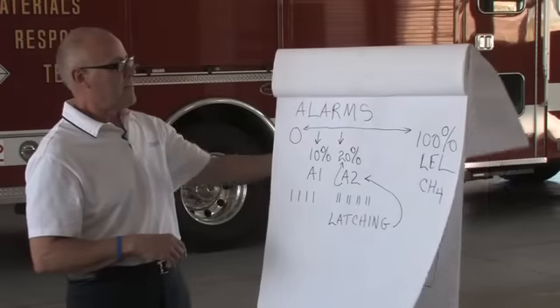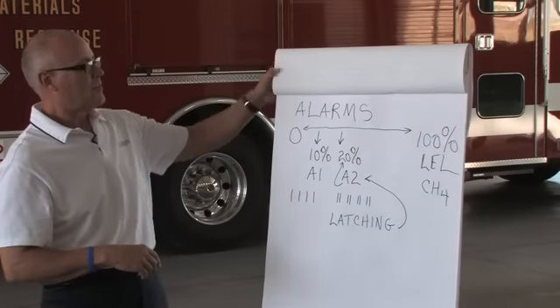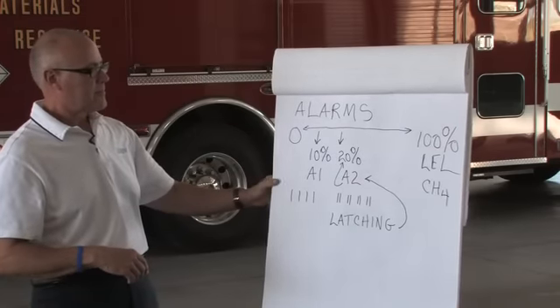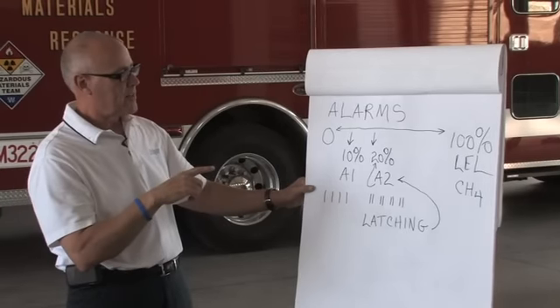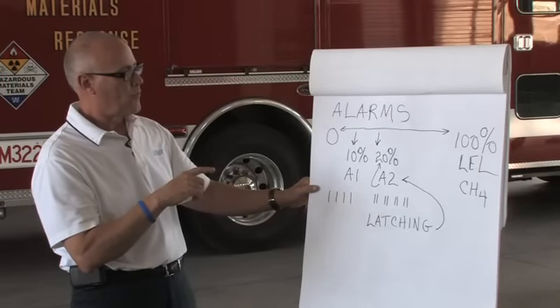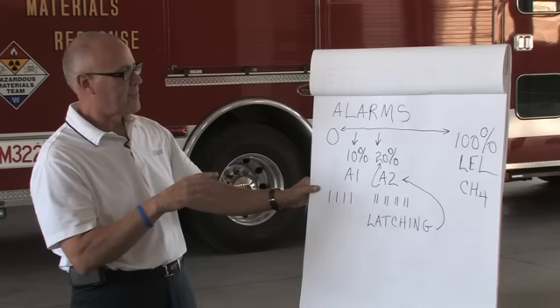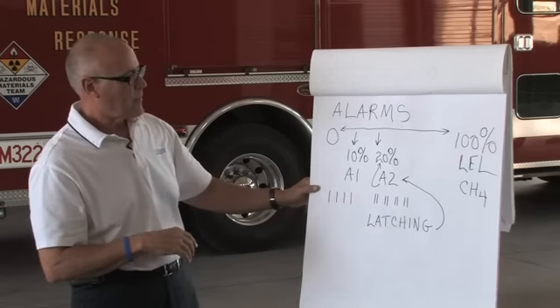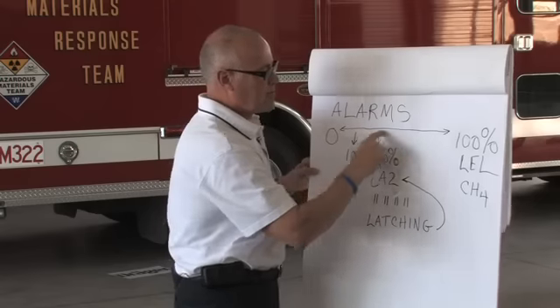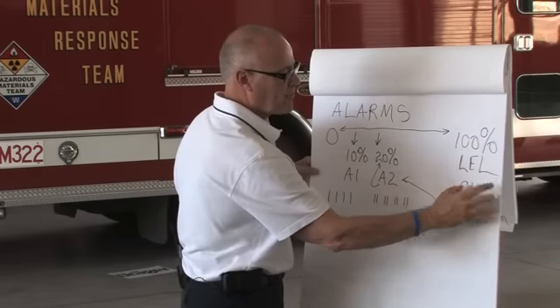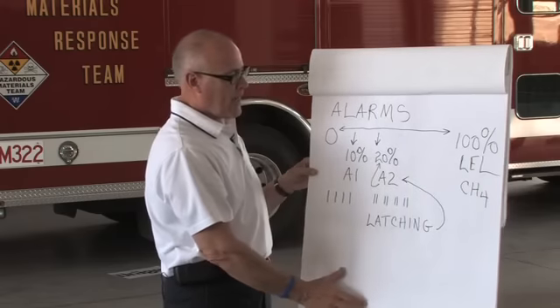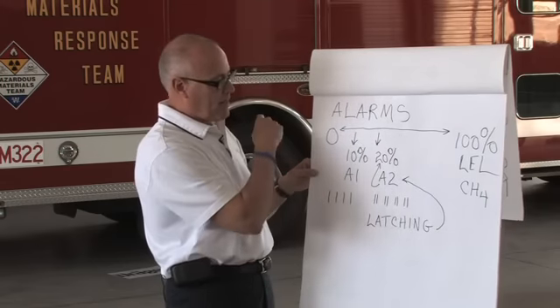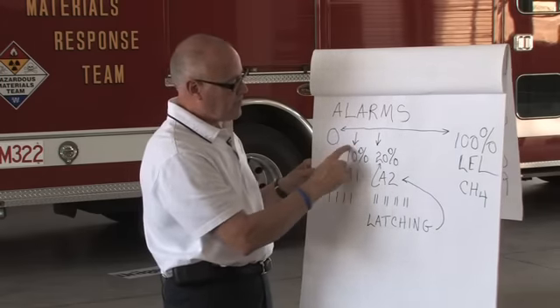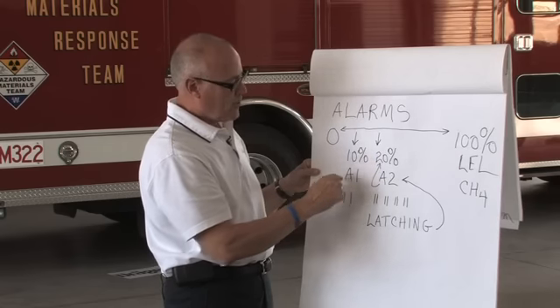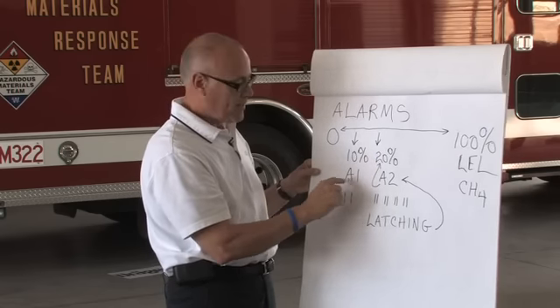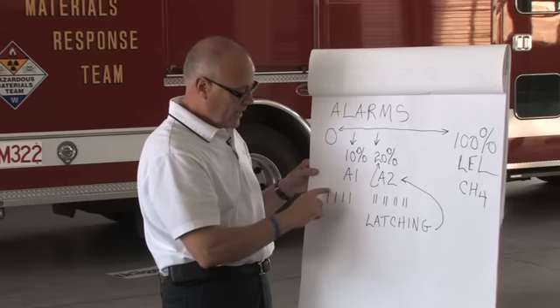Okay? This has to do with your alarms. Now, this alarm chart is again on the Wheatstone Bridge catalytic sensor, your combustible detector. And what I've got here is 0 to 100% of the lower explosive limit, methane again. And this is talking about what I was just referring to. Here's 10% of the LEL, which gives you your A1 alarm. It means alarm 1. You will get a pulse.